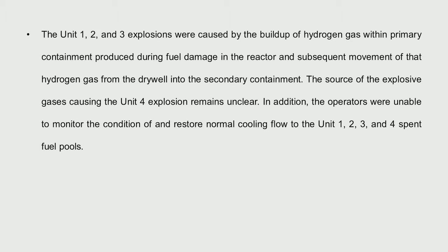The zirconium-water reaction resulted in hydrogen buildup. The buildup of hydrogen was so much that it damaged the first and second levels of containment, and then it exploded in unit 1. Not only that, even in the spent fuel bay, many fuel pins had failed because of lack of cooling and hydrogen generated. One point is very clear: in the plant design everything was okay, but for the fact that the diesel generators should have been kept at a bigger height.